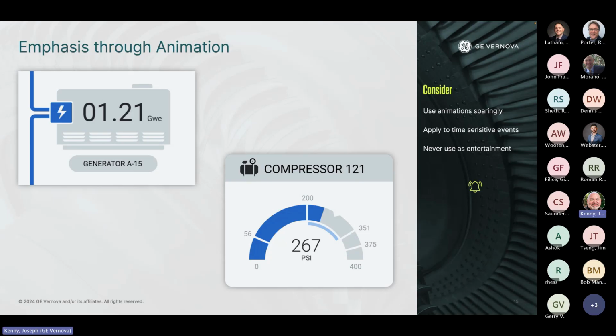Having an animation showing a spinning fan, if that has no relevance to what the operator needs to know — they just need to know the fan's on or off — it's better to use an on/off indicator than an animation, because that's visually distracting from the data they may really need to see. So that's a startup animation.